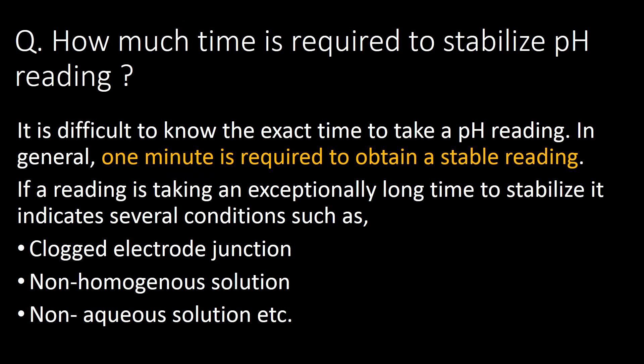How much time is required to stabilize a pH reading? It is difficult to know the exact time, but in general, one minute is required to obtain a stable reading. If a reading is taking an exceptionally long time to stabilize, it indicates several conditions such as a clogged electrode junction, non-homogeneous solution, or non-aqueous solution.